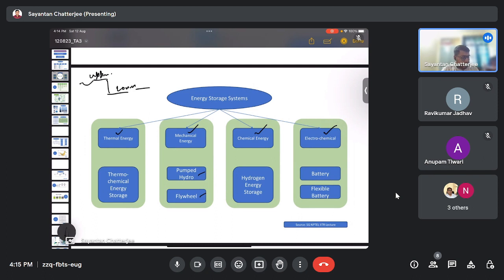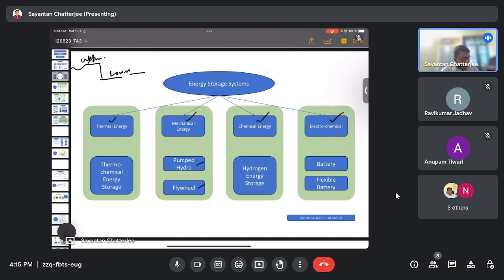This is a kind of mechanical energy storage system. The flywheel can store the inertia energy of the grid. Due to renewable penetration, the grid side inertia is being lessened, and due to this lesser inertia, sudden or abrupt falls in load can occur. During those times, flywheels try to maintain the system inertia constant by absorbing excess power from the grid.